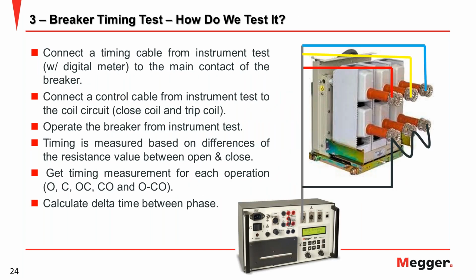How do we test it? You can see this is an example connection based on our Megger product, the Agile, but actually all equipment, not only from Megger, will provide the same connection, maybe only different on the return cable. For timing measurement, you need to connect directly to the main contacts, red, yellow, blue, and on other equipment you need to connect the return cable separately. But for the Agile, we just need to connect once to one of the return contacts, and then you need to short all the poles on the return contact.